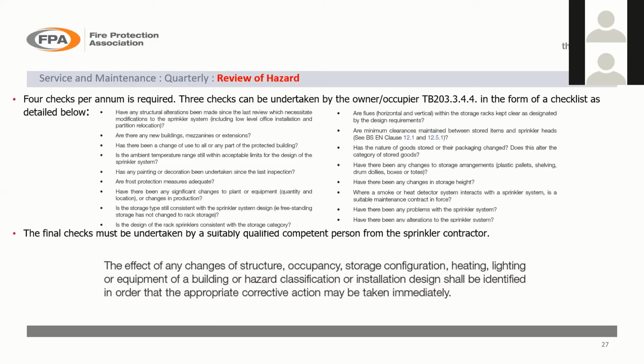So I'm just going to click on, and I've got a number of pictures which are going to come across the screen now. That was storage there. We saw a storeroom where originally storage was on the shelves, but people have started to store things onto the top shelves. So basically what's happened is there's no clear space between the sprinklers at roof level, and obviously the sprinklers are blinded and they won't operate, or they'll operate slowly, or the water spray discharge will be affected. So clearly the top level of boxes needs to be taken off the shelving.